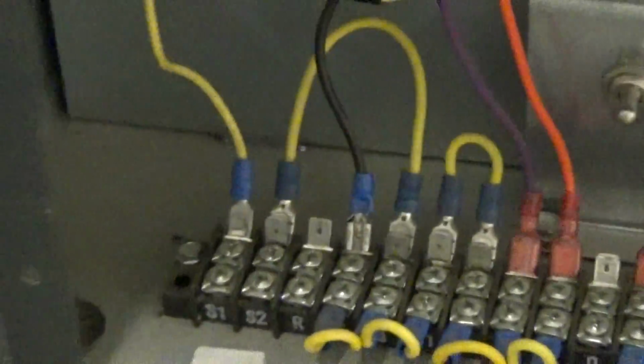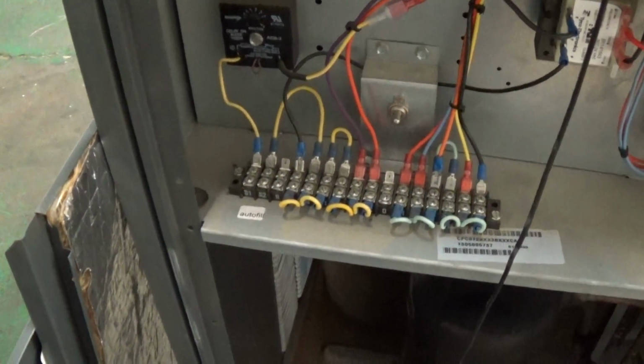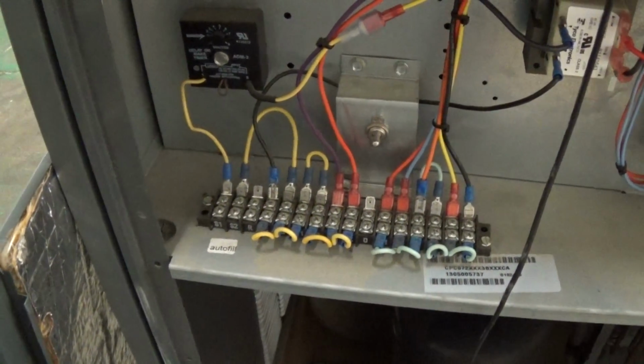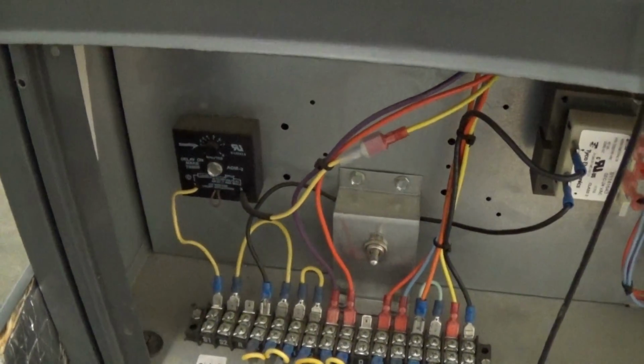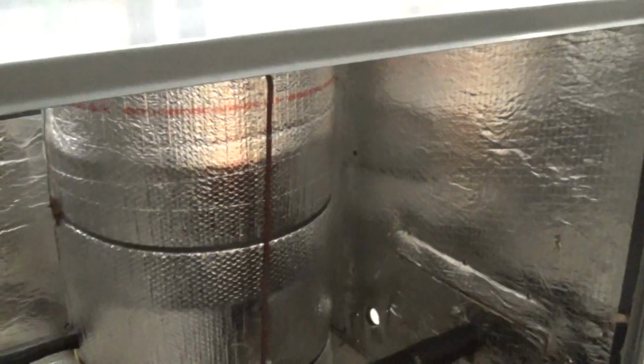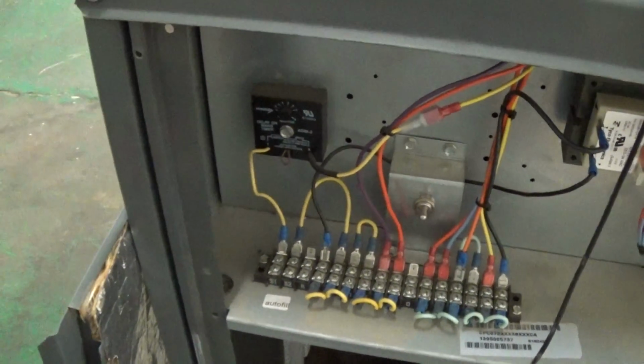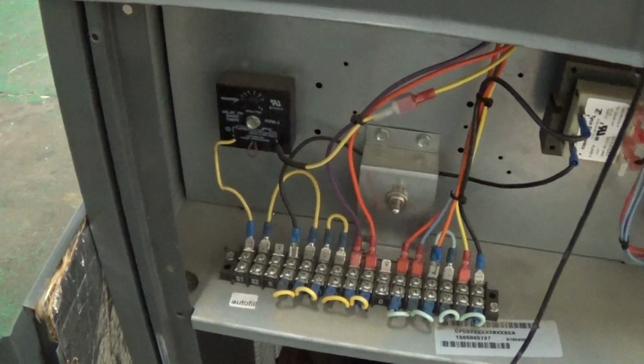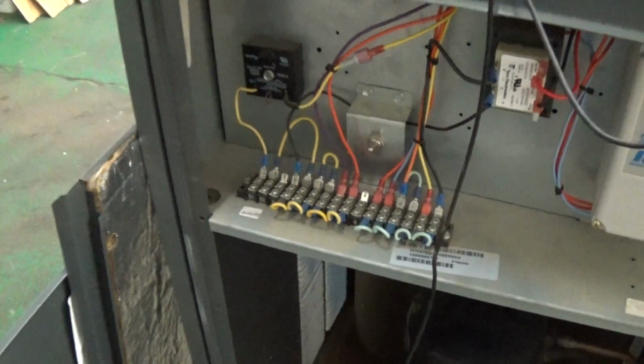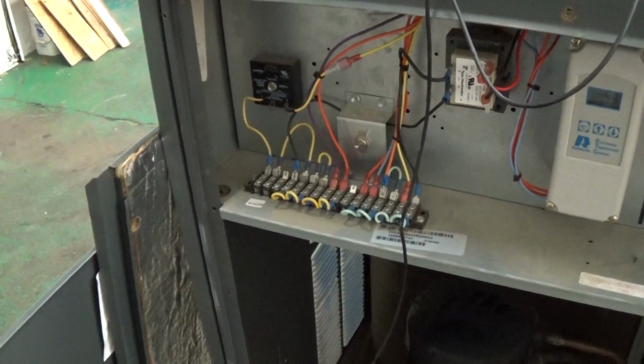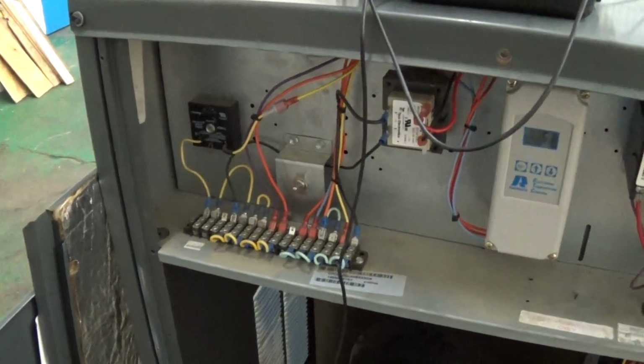Here on our insulated stainless tank, this is actually the float switch, and it's kind of a nice thing that they do. The customer can choose what to connect up, but here at the terminal strip, you have a 24 volt AC contactor, or contacts, and that goes through a little delay timer. So when the tank gets low, not dangerously low, but when the tank gets low, you can make a signal here after the timer is met, so you don't get any type of chattering effect. You can make a signal to activate either a buzzer or a light. Ideally, or most likely, you want to bring the 2 terminals, the 2 wires into the building, just so you can be prompted if the fluid level were to get low.